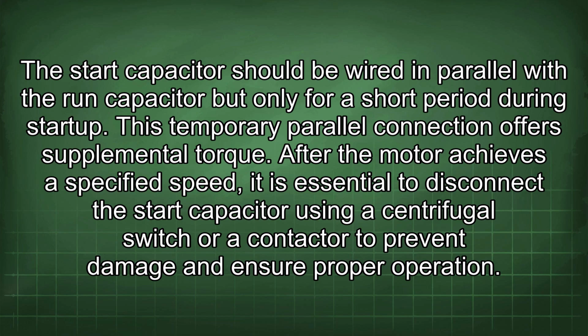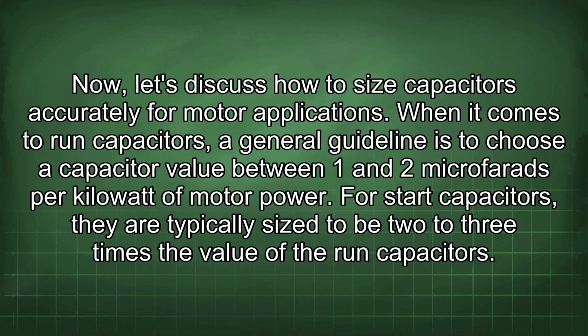After the motor achieves the specified speed, it is essential to disconnect the start capacitor using a centrifugal switch or a contactor to prevent damage and ensure proper operation. Now let's discuss how to size capacitors accurately for motor applications. When it comes to run capacitors, a general guideline is to choose a capacitor value between 1 and 2 microfarads per kilowatt of motor power.